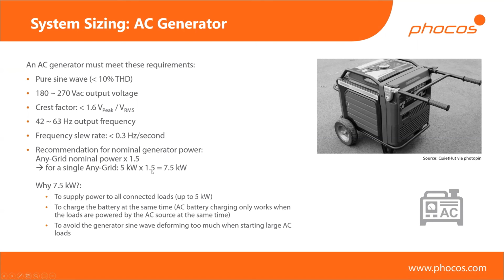And we recommend to have 1.5 times the nominal power of the inverter as a generator size. And the reason is quite simple. When you're working in AC or in grid mode, even though technically speaking this is not a grid, it's an AC generator, then you need to be able to power all of your loads, and at the same time, if you're charging your battery, you need to be able to do that simultaneously. So if you're charging your battery with say 2 kilowatts, then you need to make sure that you can have another 5 kilowatts to power your loads. So you'll end up with about 7.5 kilowatts of power that your AC generator should be able to deliver.